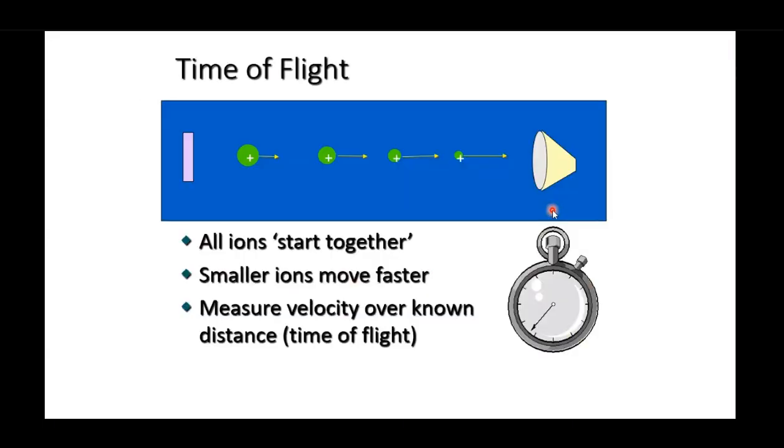Time of flight is very useful as it gives you high resolution. It can give you the molecular weight information up to the 4th decimal level, and that gives it some specificity, because when you are working with some unknown metabolites, unknown impurities, if you get molecular weight information up to the 4th decimal level, it definitely gives you an added advantage that you can come closer to the structure of the compound which you are measuring. So time of flight is a very good mass analyzer, which gives you high mass accuracy.